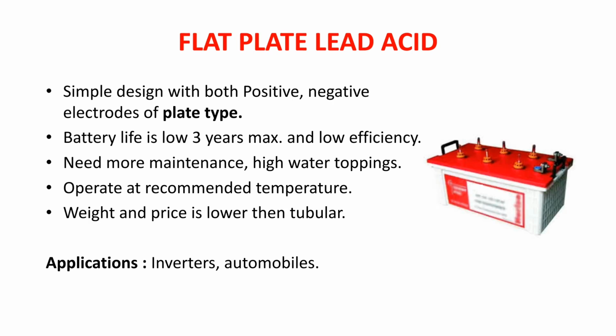Now we will see the flooded lead acid batteries or wet cells in detail. First one is the flat plate lead acid battery. In this type of battery, the positive electrode and the negative electrode are both of plate type, meaning both electrodes have a plate shape, not the plates we have in our kitchen but rectangular. These types of batteries require high maintenance, meaning water needs to be filled in these batteries regularly, mainly every 3 months. And these batteries have low life expectancy and low efficiency.